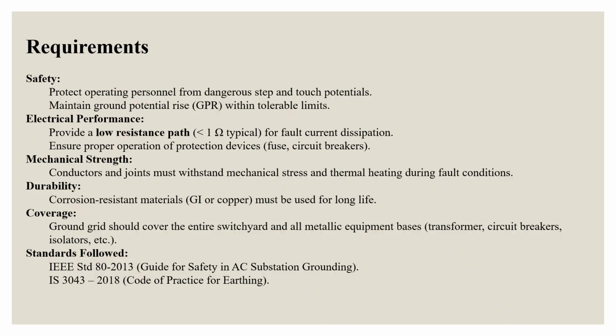For an earthing grid to be effective, it must satisfy certain requirements. It must provide safety by maintaining step and touch voltages within limits and controlling ground potential rise. It must have good electrical performance, which means the grid resistance should typically be less than 1 ohm to ensure proper fault dissipation. It must also have mechanical strength to withstand high fault currents and durability against corrosion, using copper or galvanized iron. Lastly, it should cover the entire substation area, connecting all metallic structures and equipment bases.